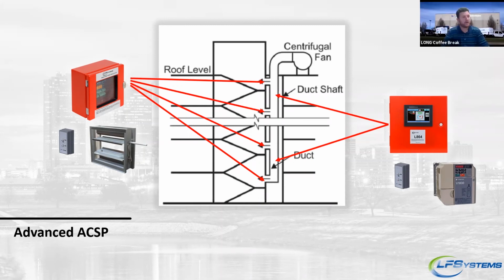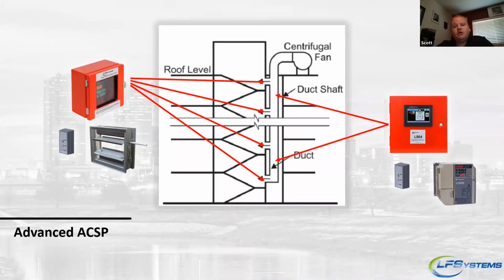Okay. And as far as functionality and operation, can the L864 controller manage multiple stairwells? And how does this look in a fire alarm control panel room? So the L864 is dedicated per stairwell. So you would have one 864 per stairwell. And basically they would all be lined up beside the FSCS. And the fireman could go through there and see each stairwell and what it was doing in real time. Okay.